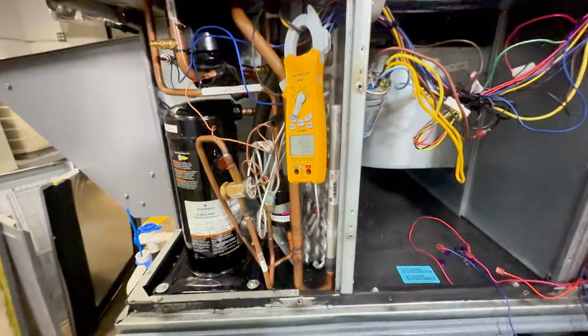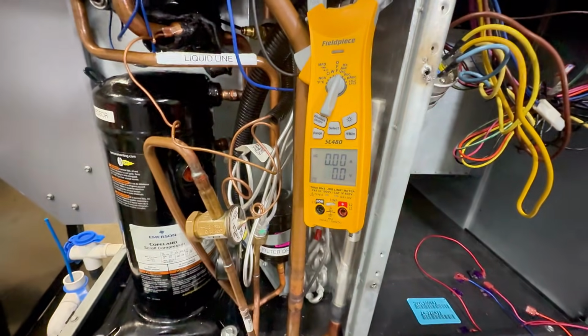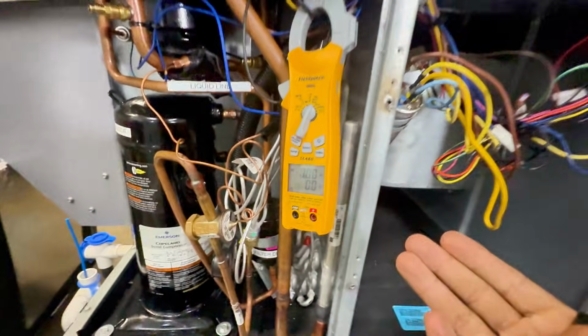You see 0.64/0.71. So it should be around there, right? But it's 0.64. So full load amps, 0.64. And I think the reason why it gives us 2 different amp draws is because it can take 208 or 230. So since we're powering it up with 208, it should be 0.64 or close to it. Okay, remember that number, 0.64, okay? So now let's go ahead and turn on the condenser fan, right?